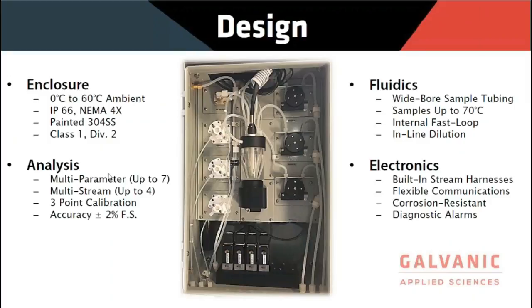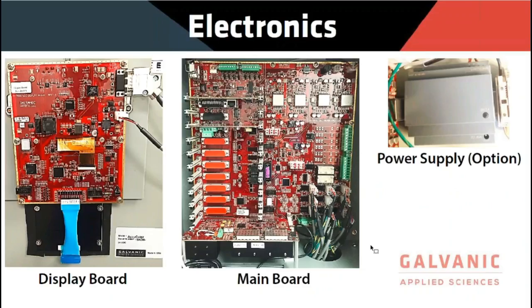For the fluidics, we have a wide bore sample tubing, which means we can handle higher turbidity as well as suspended solids. Samples up to 70 degrees Celsius, and we can also do hotter with sample cooling or different materials chosen. We have an internal fast loop, so there's always a fresh, repeatable sample. And we have inline dilution available if we need to dilute for higher ranges. As I mentioned, we can do up to 4 streams, and all of these systems have built-in stream harnesses. So if you ever needed to upgrade from 1 stream to 2 streams, all you need is the valve. Everything else is already built in. Flexible communications, corrosion-resistant boards, as well as diagnostics alarms. We have the display board as well as the main board, and everything is plug and play.